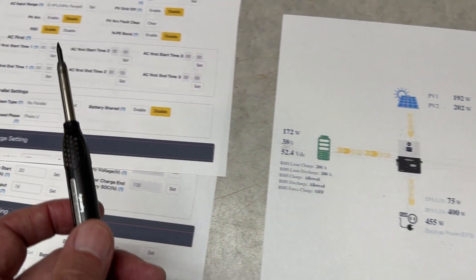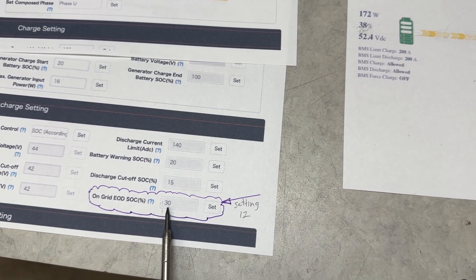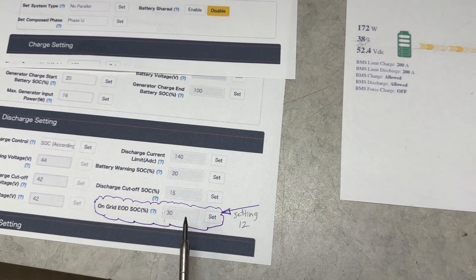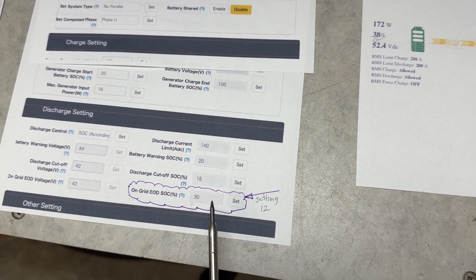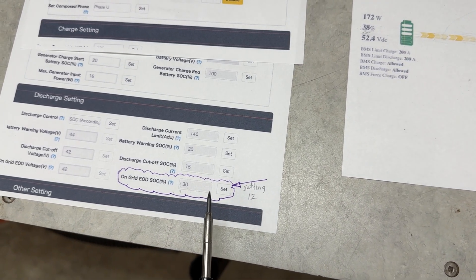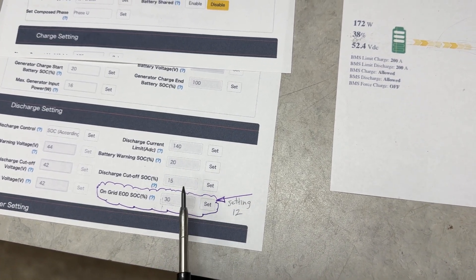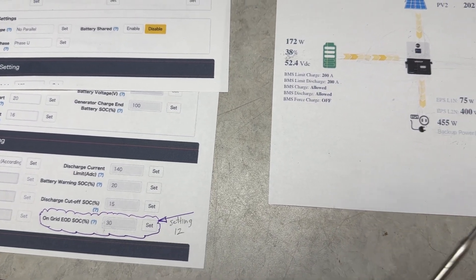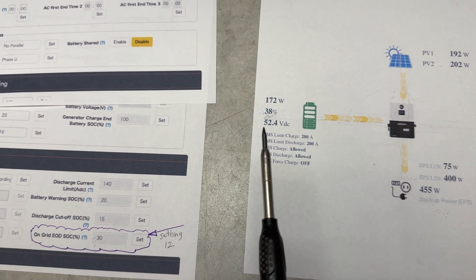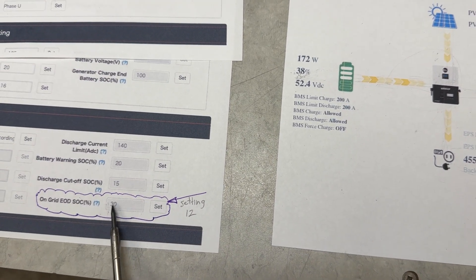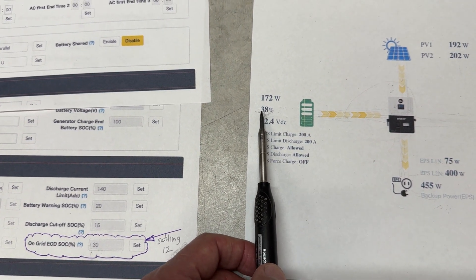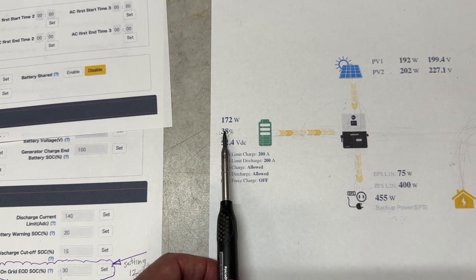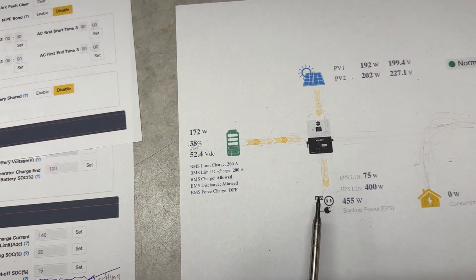The other thing is you can play around with this setting if you know something is coming up in the near future. For example, my utility has informed us they will be shutting power down on a particular date because they're going to replace some old power poles. If on that day it's a rainy day, a day or two before that I can increase this to say 50 or so, so that I don't get below 50, such that when the power is shut off I have enough buffer here to supply power to my house for the few hours, like six hours or so, that the power will be out.